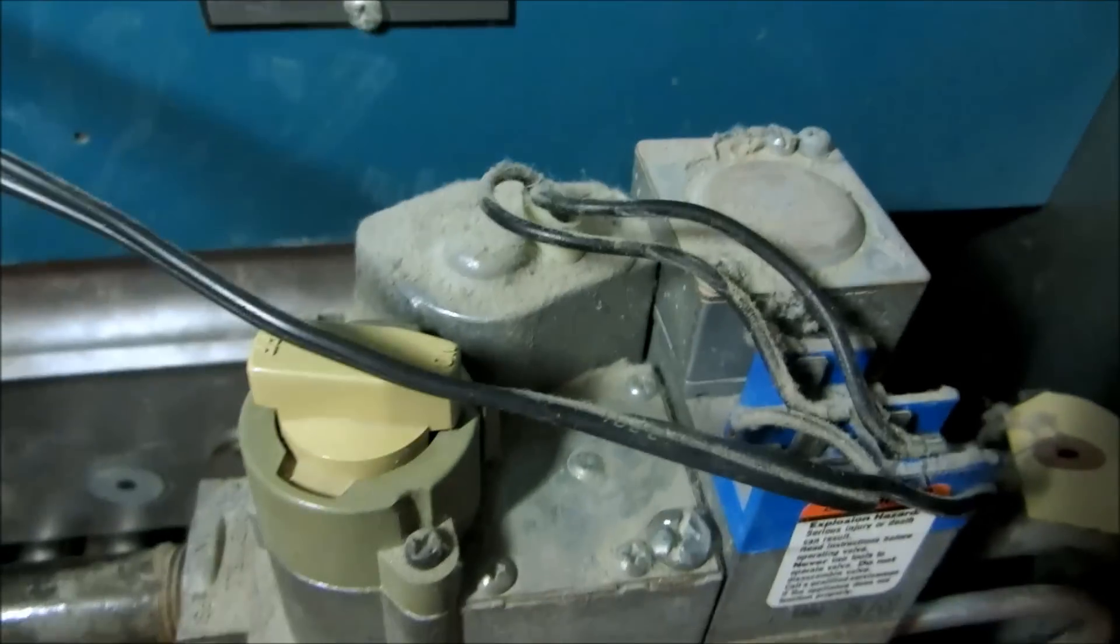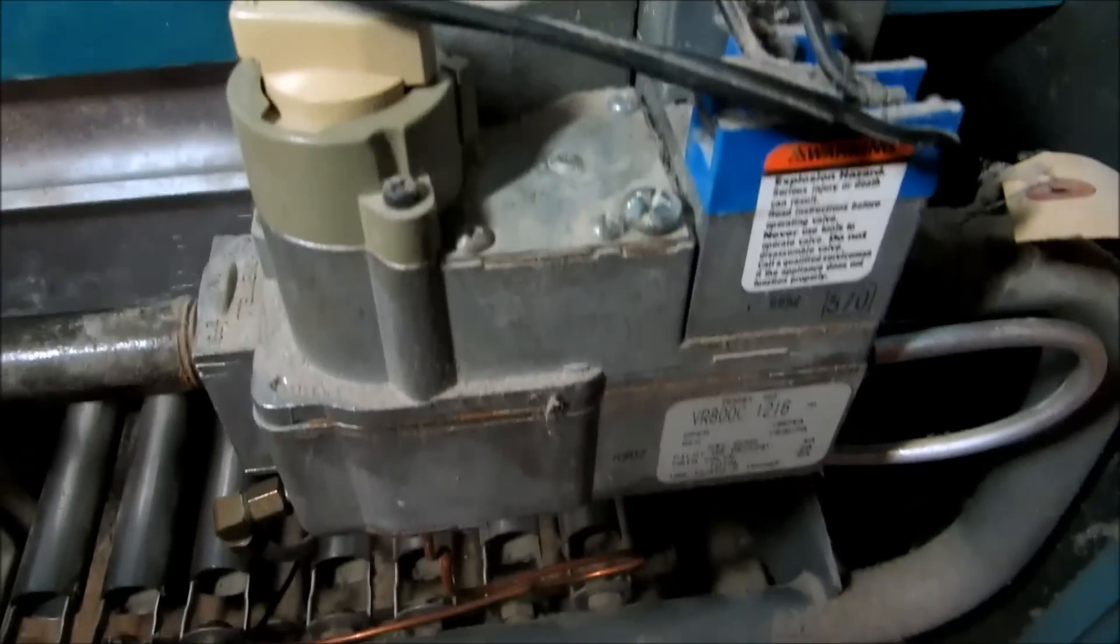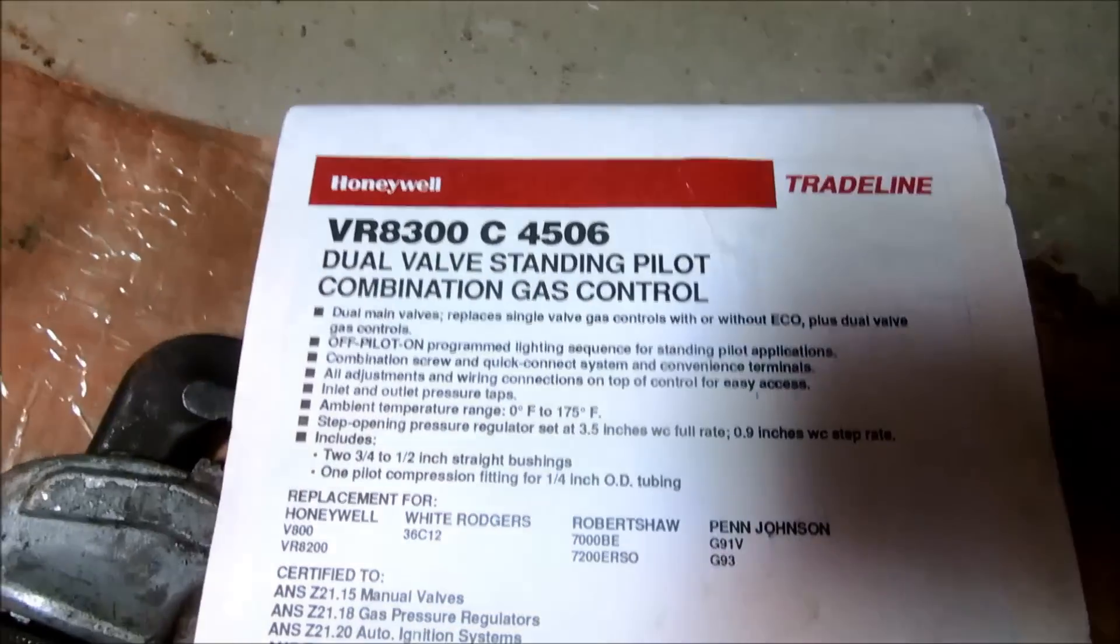I'm going to change this gas valve. It's non-adjustable, high CO levels, a replacement here.